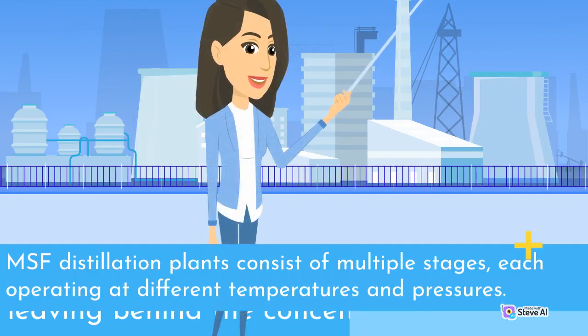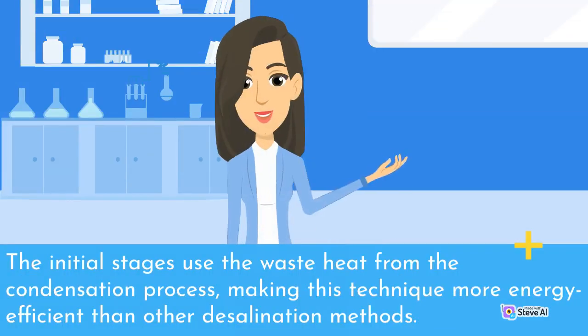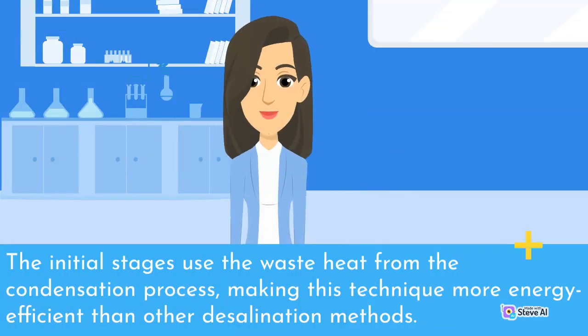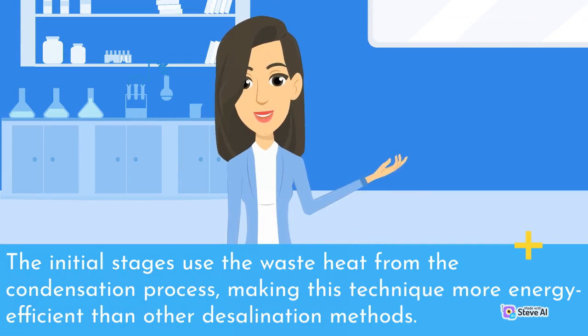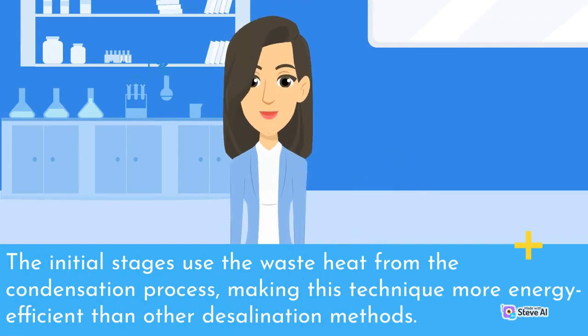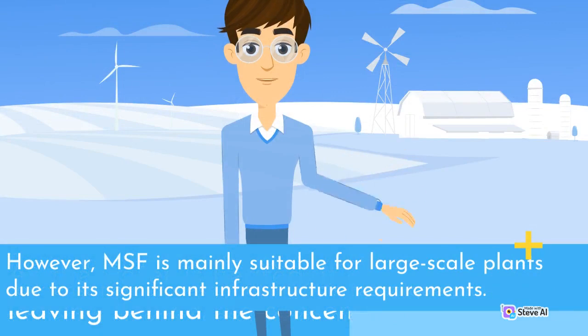MSF distillation plants consist of multiple stages, each operating at different temperatures and pressures. The initial stages use the waste heat from the condensation process, making this technique more energy efficient than other desalination methods. However, MSF is mainly suitable for large-scale plants due to its significant infrastructure requirements.